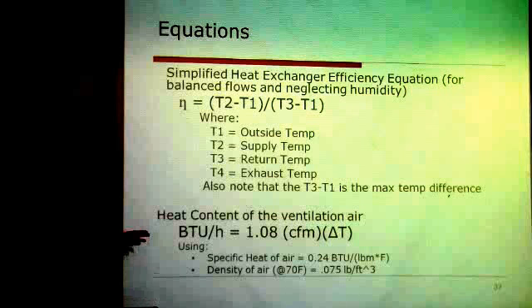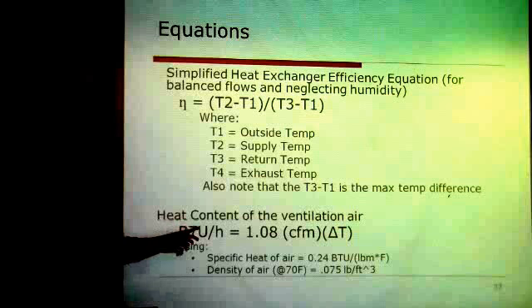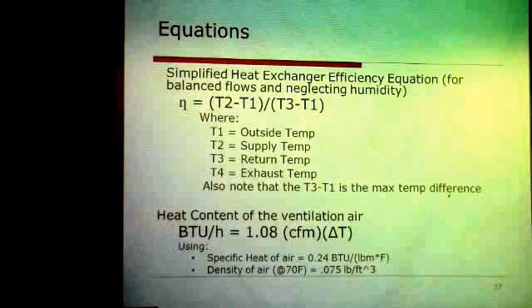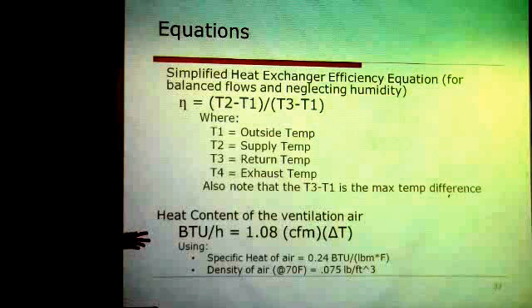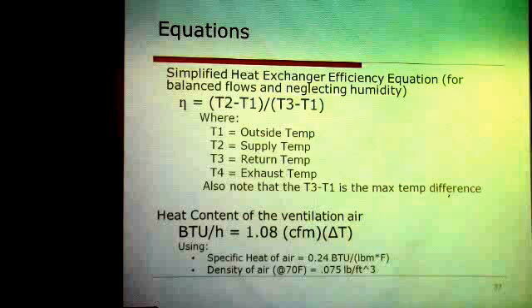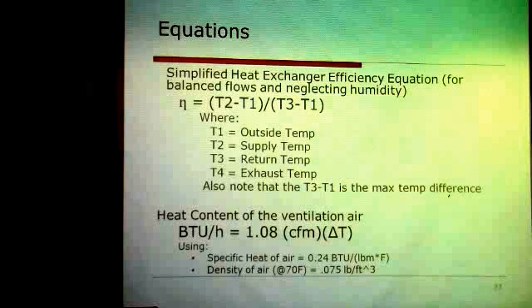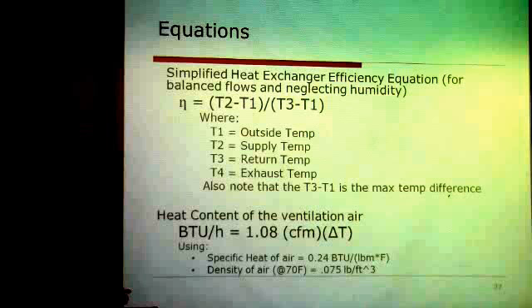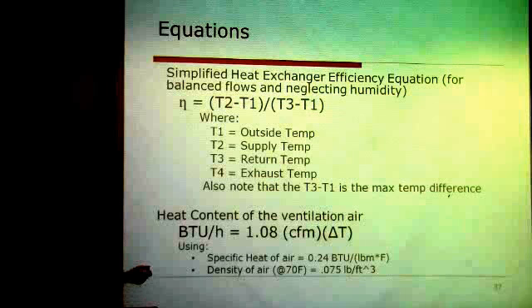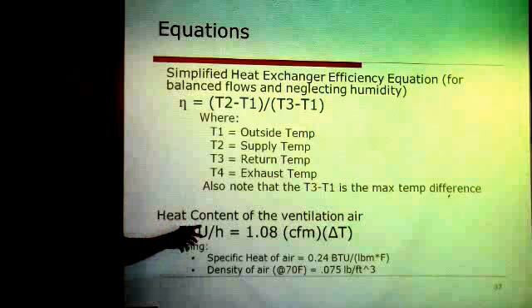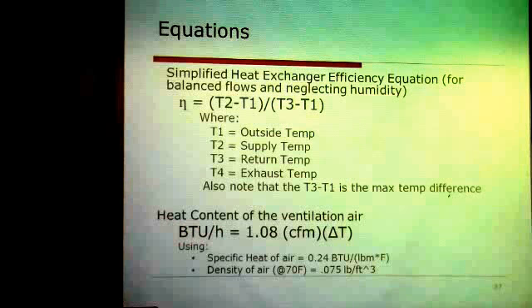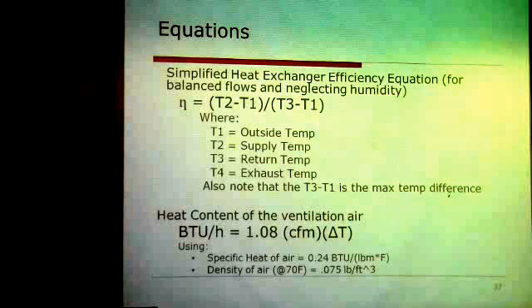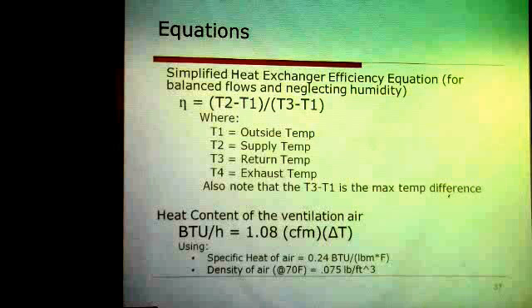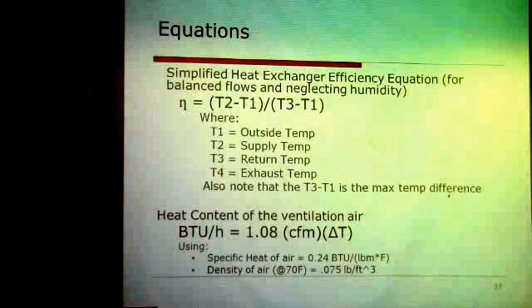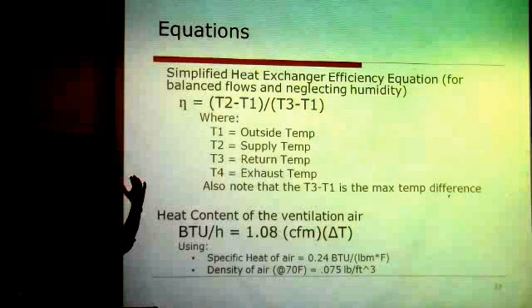Another thing we talked about a little bit is the heat content. I think it should be 1.085, but this basically just tells you how much heat that airstream can carry. So a lot of people say, well, why can't you heat the house through the ventilation air? So then you have to look at how much that is. When you're heating, say the air is coming in from the HRV at 65, and then you add a downstream heater to heat it up to about 120. So that's a 55-degree delta.